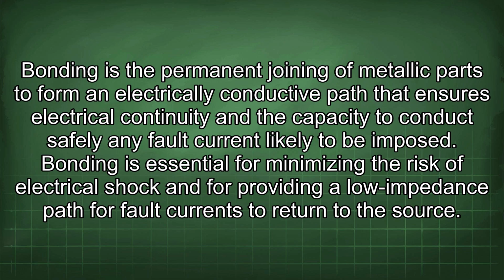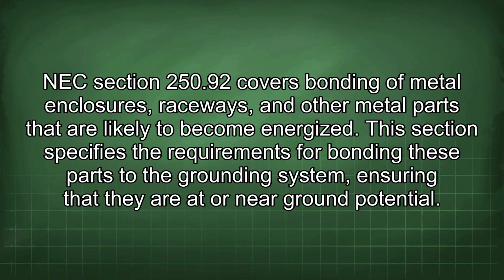Bonding is essential for minimizing the risk of electrical shock and for providing a low impedance path for fault currents to return to the source. NEC Section 250.92 covers bonding of metal enclosures, raceways, and other metal parts that are likely to become energized.